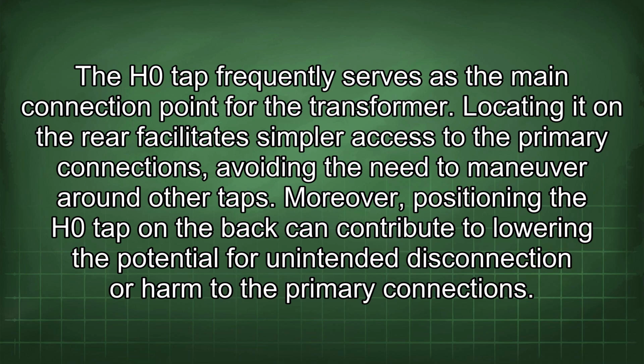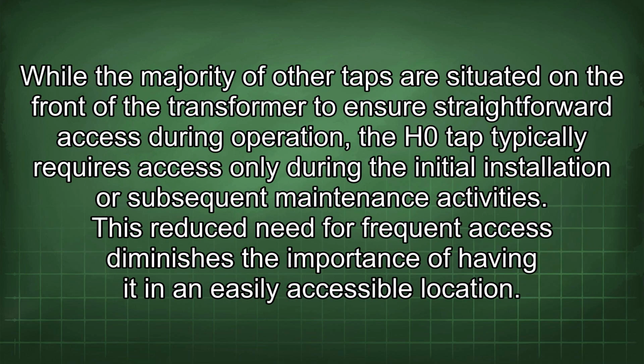Locating it on the rear facilitates simpler access to the primary connections, avoiding the need to maneuver around other taps. Moreover, positioning the H0 tap on the back can contribute to lowering the potential for unintended disconnection or harm to the primary connections, while the majority of other taps are situated on the front of the transformer to ensure straightforward access during operation. The H0 tap typically requires access only during the initial installation or subsequent maintenance activities.